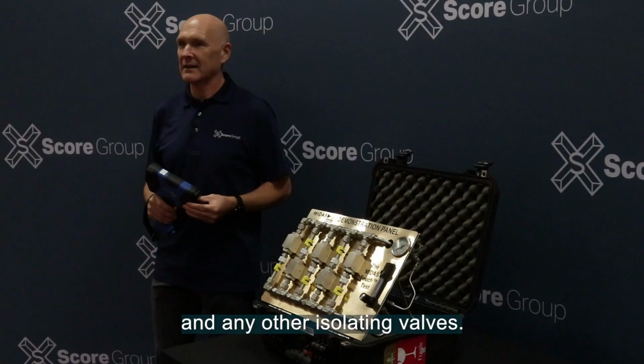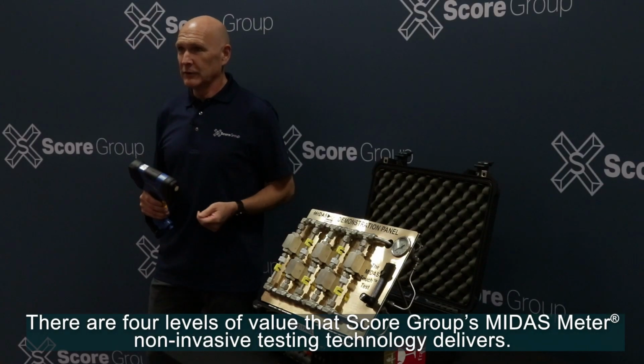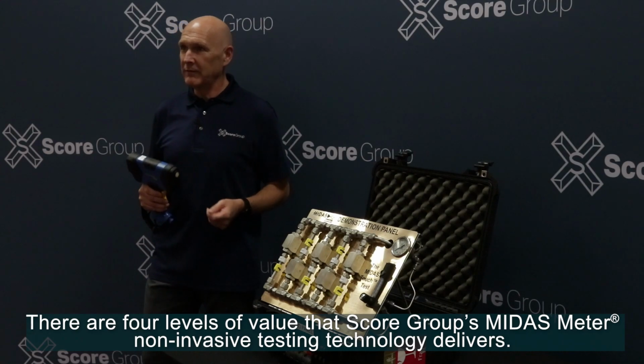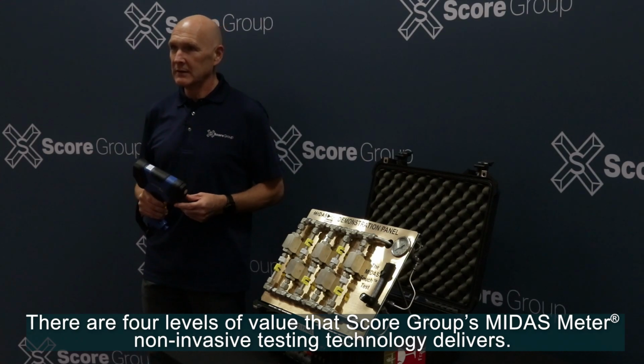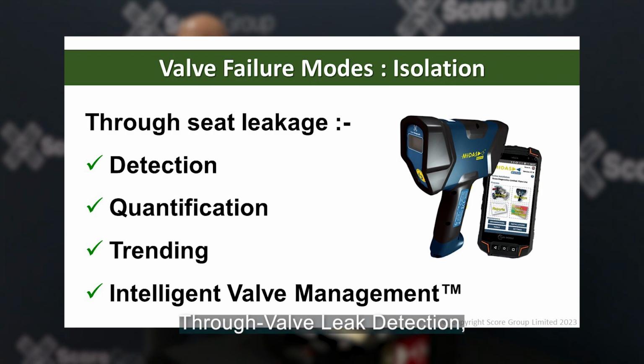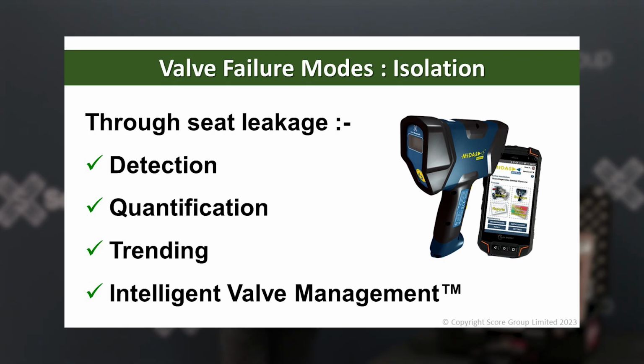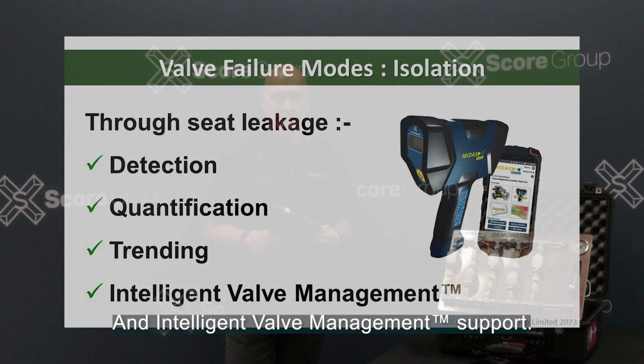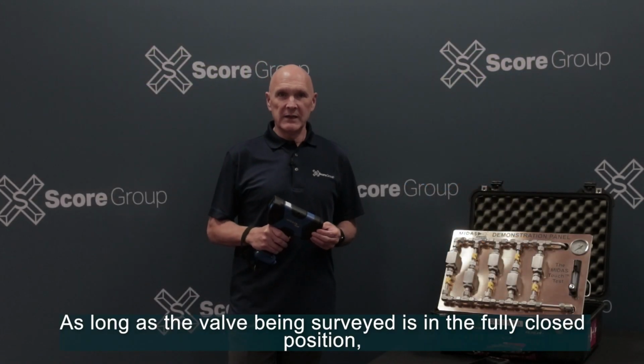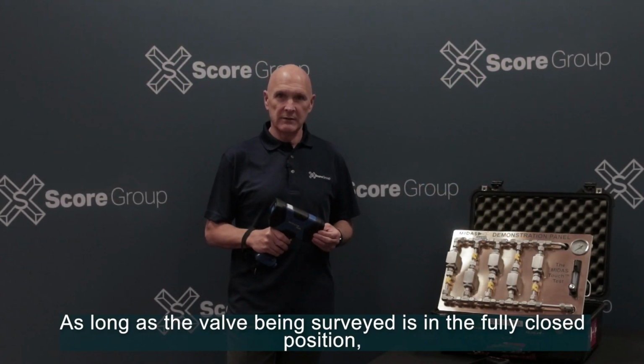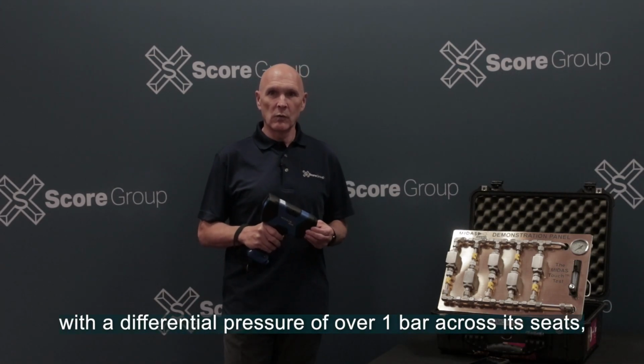isolating valves. There are 4 levels of value that Score Group's MIDAS meter non-invasive testing technology delivers. These are through valve leak detection, through valve leak rate quantification, through valve leak rate trending, and intelligent valve management support. As long as the valve being surveyed is in the fully closed position with a differential pressure over 1 bar across its seats, then MIDAS meter can be used to survey performance and deliver quantifiable value.